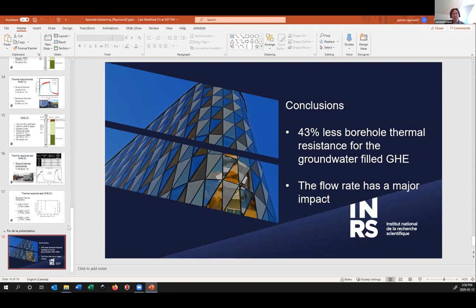In those kinds of systems, you can expect about 40–50% of heat loss in the ground, but still, yes, you can recover by having a tight bundle of ground heat exchangers. In the regular geothermal heat pump system, you want your boreholes to be far apart from each other, so there is no thermal interference, while for thermal energy storage, you want the boreholes to be closely spaced together. So actually, you inject heat in the middle and you recover it by the sides.